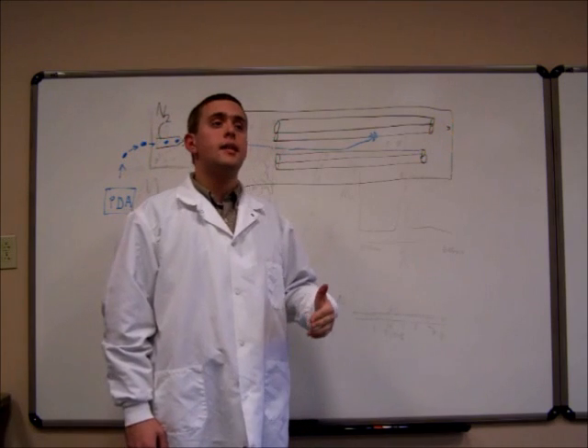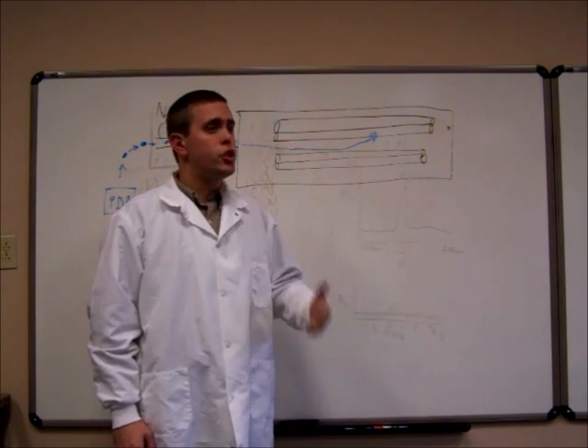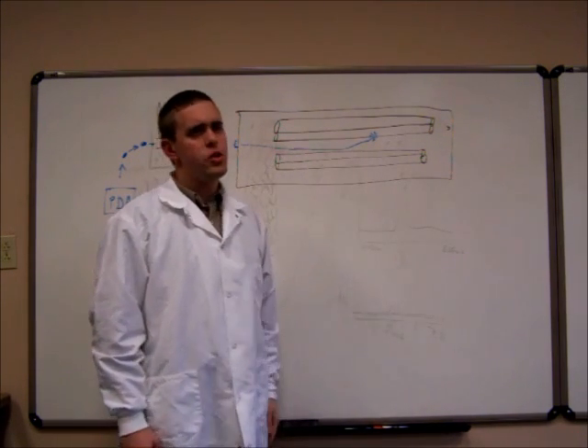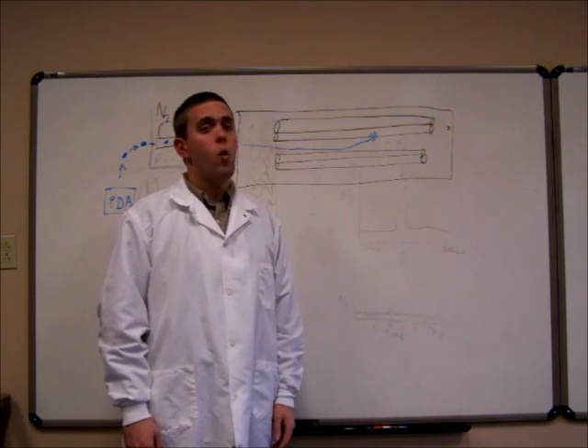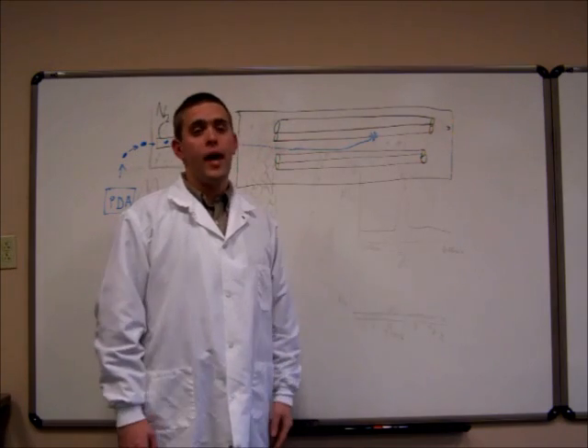And when that happens, the analyte is trapped. It's not destroyed. It's just permanently entombed, stuck, glued to, never coming off again, the quadrupole. This analyte will no longer be analyzed.